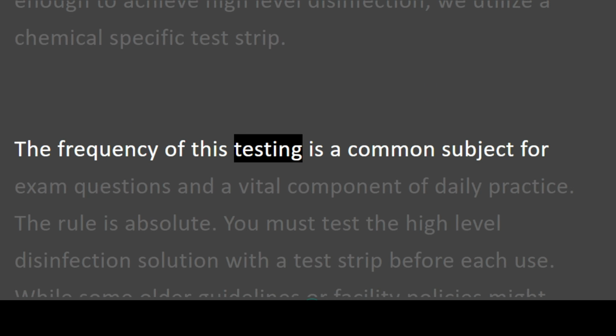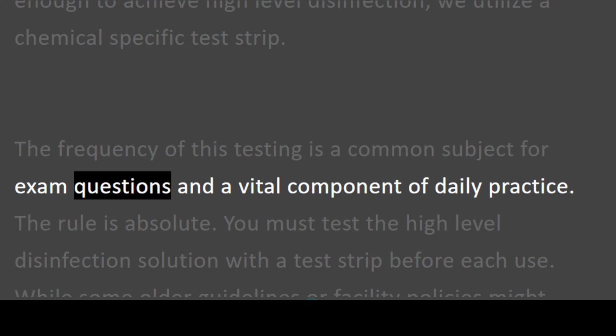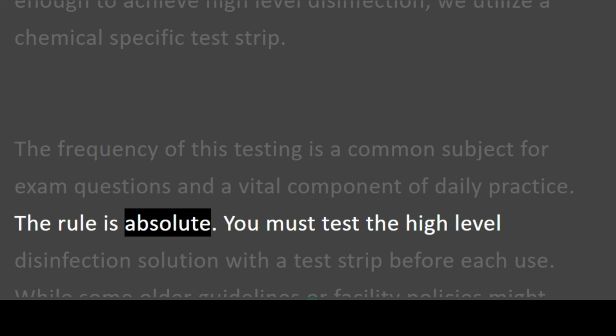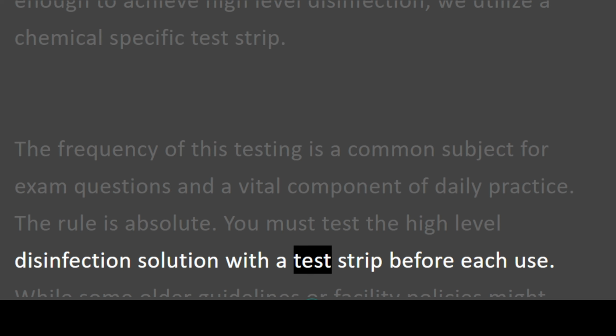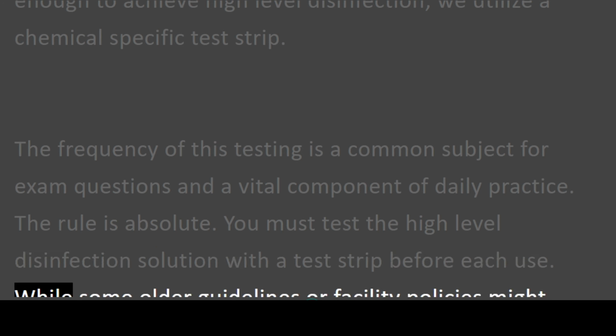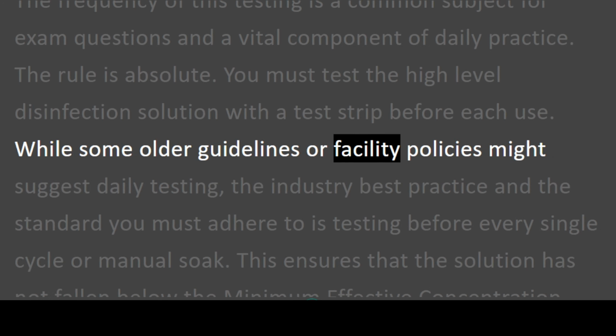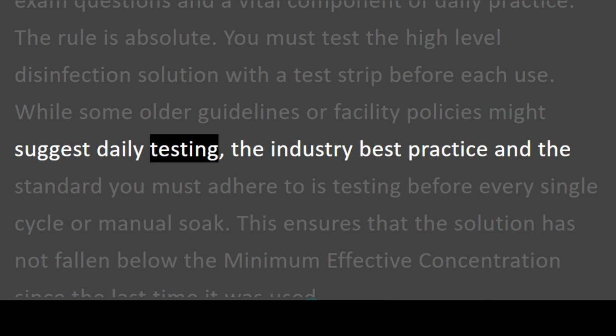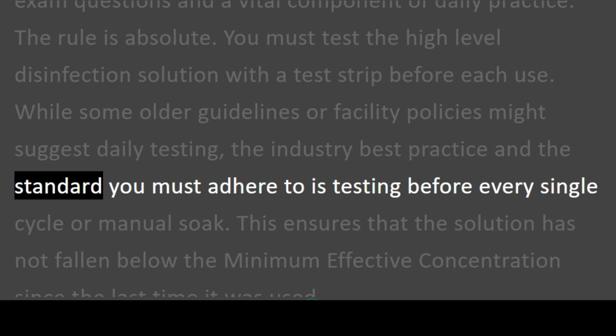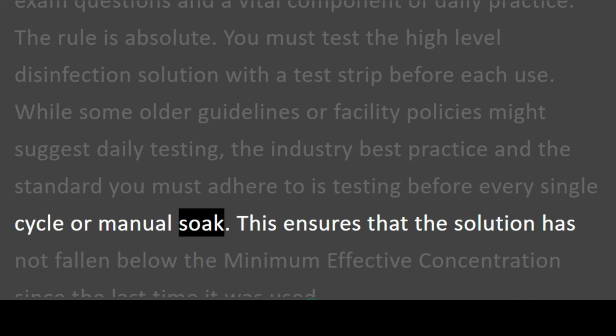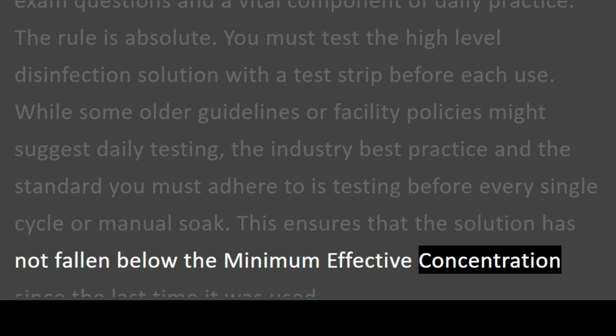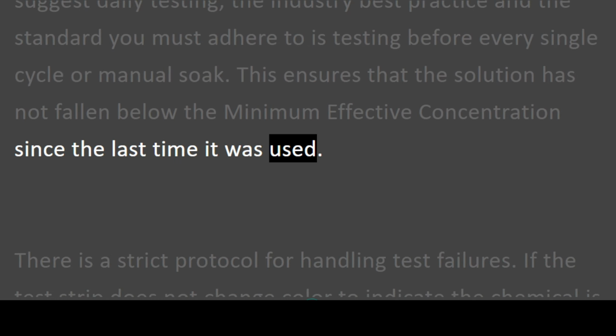The frequency of this testing is a common subject for exam questions and a vital component of daily practice. The rule is absolute. You must test the high-level disinfection solution with a test strip before each use. While some older guidelines or facility policies might suggest daily testing, the industry best practice and the standard you must adhere to is testing before every single cycle or manual soak. This ensures that the solution has not fallen below the minimum effective concentration since the last time it was used.